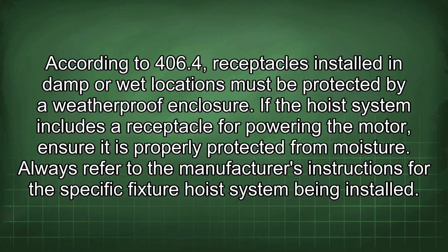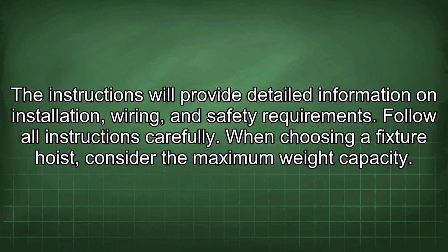According to 406.4, receptacles installed in damp or wet locations must be protected by a weatherproof enclosure. If the hoist system includes a receptacle for powering the motor, ensure it is properly protected from moisture. Always refer to the manufacturer's instructions for the specific fixture hoist system being installed. The instructions will provide detailed information on installation, wiring, and safety requirements. Follow all instructions carefully.